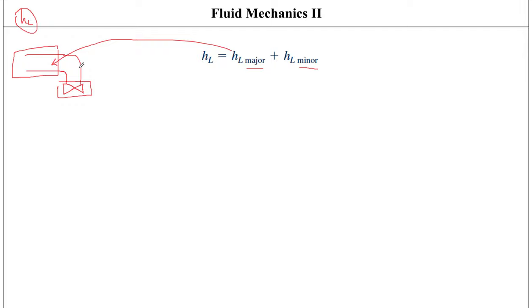An important distinction: major and minor here do not represent that one is more important than the other. Major loss indicates losses within straight pipes, minor losses indicate losses within pipe components. In many applications, especially where a piping system has a lot of components and not much straight pipe length, the minor head losses can be relatively much higher than the major head losses.